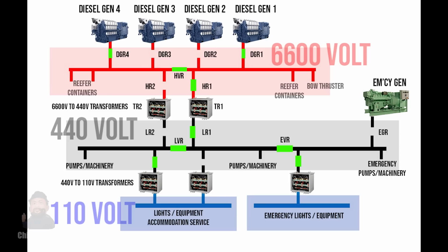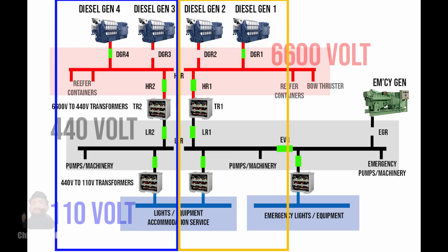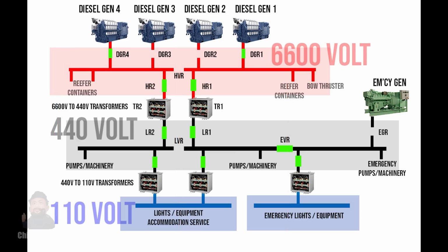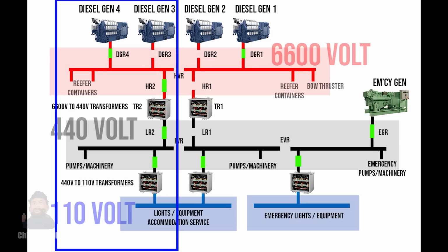In the previous episode, I gave a simple explanation of the container ship Dali's electrical distribution system. A lot of you have noted that the high voltage bus and the low voltage bus can be split into two by switching their respective bus tie breakers into open position. This way, in case one transformer fails, as it seems to have been the case with the Dali, a blackout won't occur and the main engine can be kept running since the other transformer will still be able to provide electricity to the 440 volt bus where every critical machinery related to the ship's propulsion is connected. That is actually a great idea. But why is this not standard practice for cargo ships when entering or leaving harbor?